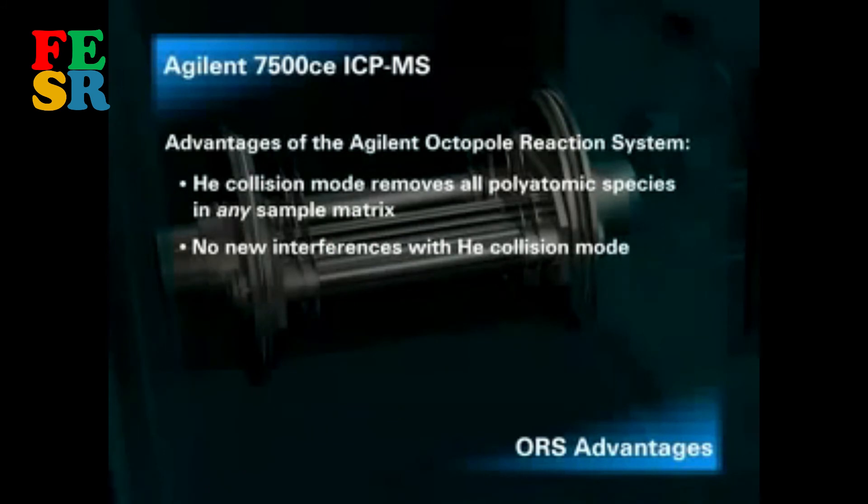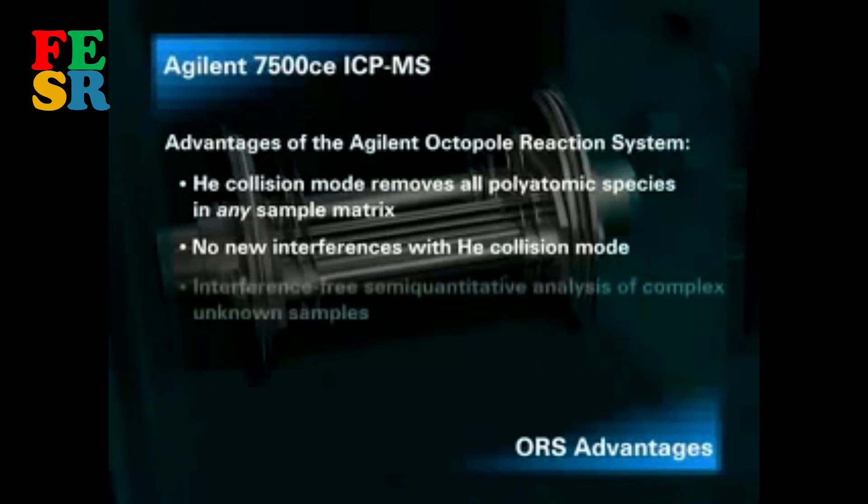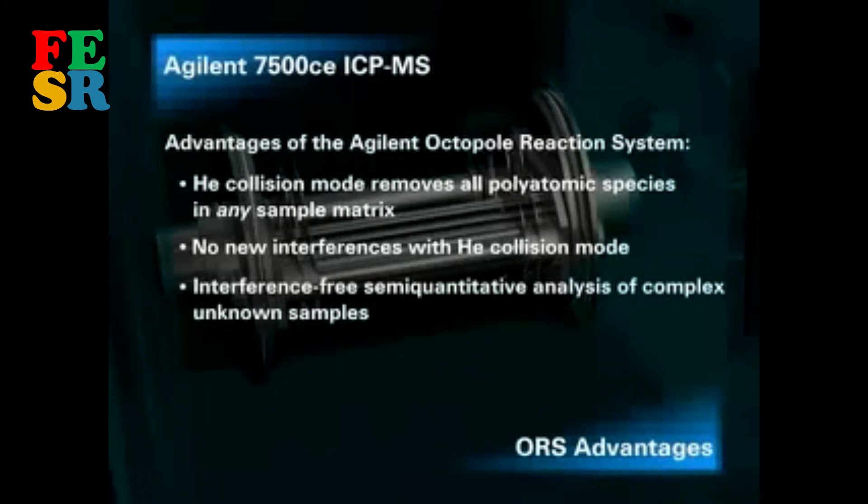Reactive gases are not suitable for multi-element analysis in complex sample matrices, since they react with the sample matrix, forming new interferences in the cell, which can bias analytical data. Helium collision mode enables rapid and accurate semi-quantitative analysis. More than 60 elements can be measured in a completely unknown sample in approximately one minute, without the need to run calibration standards.